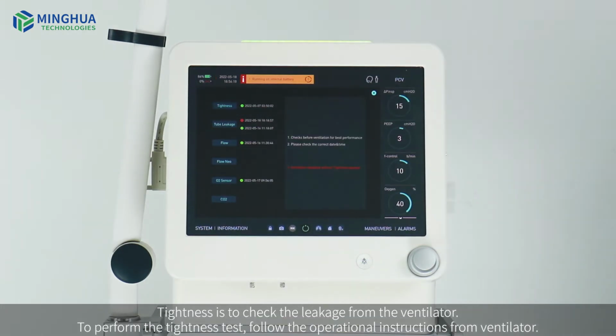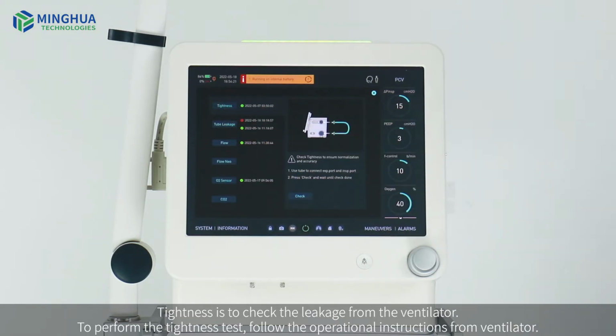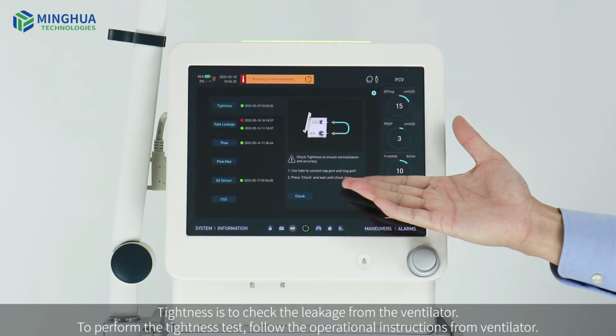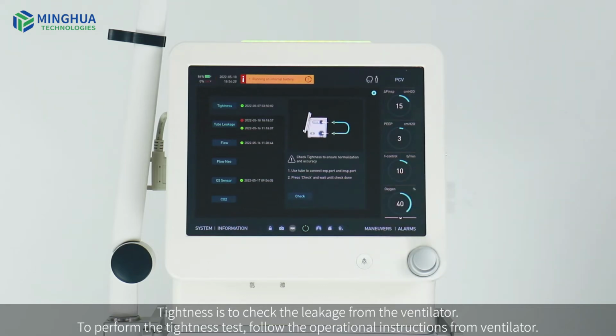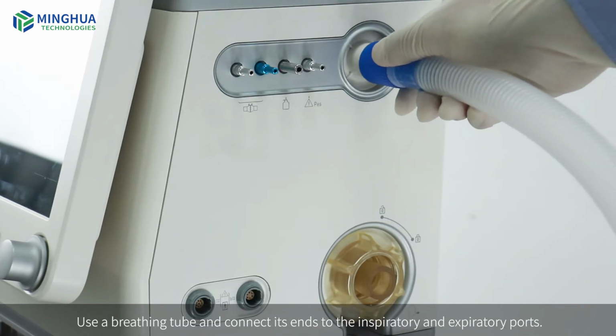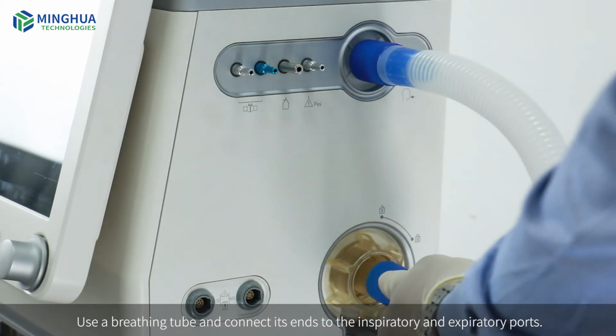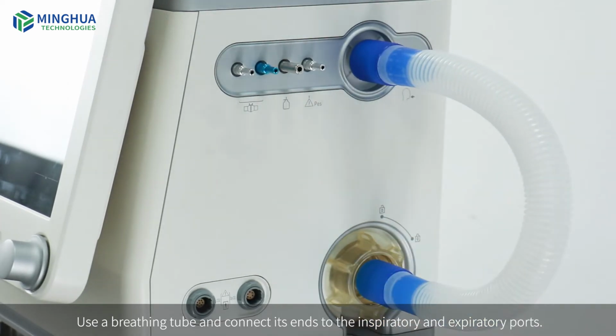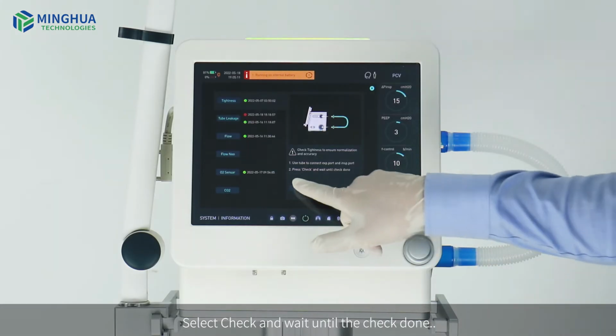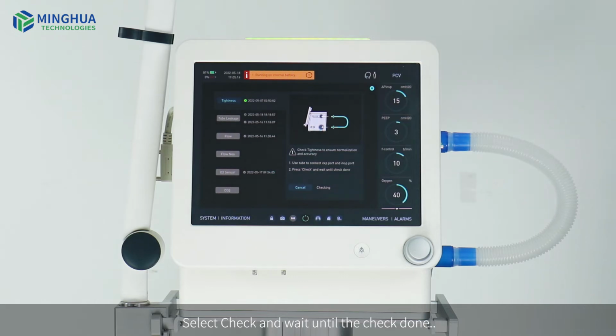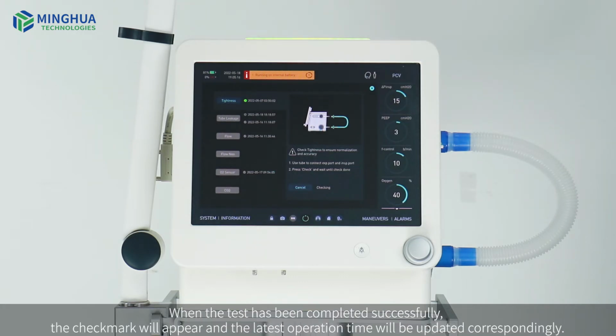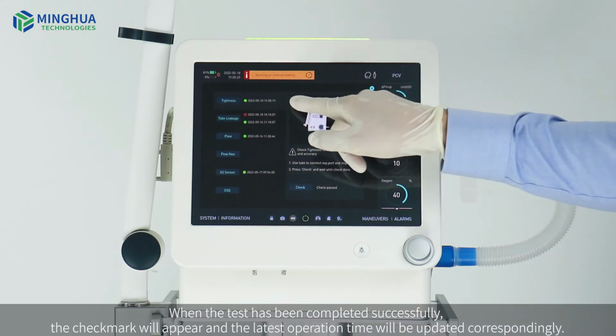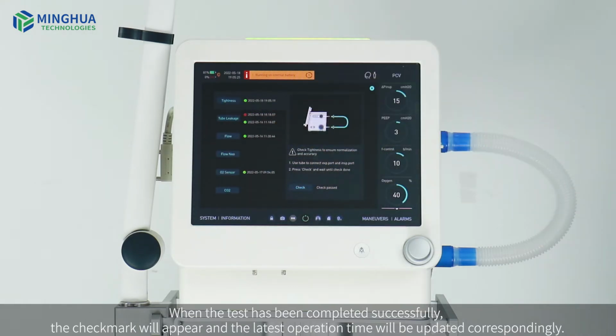Tightness is to check the leakage from the ventilator. To perform the tightness test, follow the operational instructions from ventilator. Use a breathing tube and connect its end to the inspiratory and expiratory ports. Select Check and wait until the check done. When the test has been completed successfully, the check mark will appear and the latest operation time will be updated correspondingly.